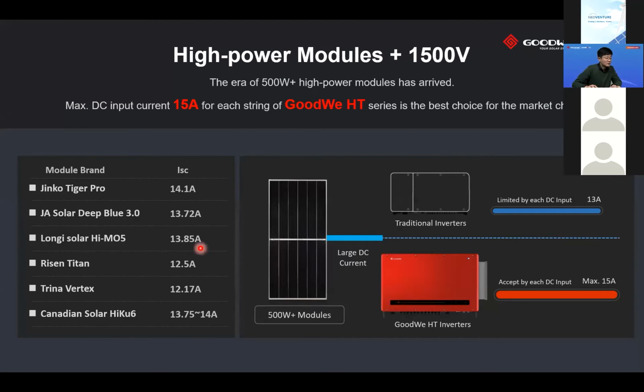And with our HT products, you see that we have more and more of the most popular PV module makers presenting their new generation products, and their ISC, the input current, is getting higher and higher. With our HT products, we can fully achieve that, even with a DC input current up to 15 amperes. Compared with traditional inverters, if their DC input only handles 13 amperes, that will make the PV projects not run fully. But with our maximum 15 amperes DC input current design, we can fully run these PV modules.